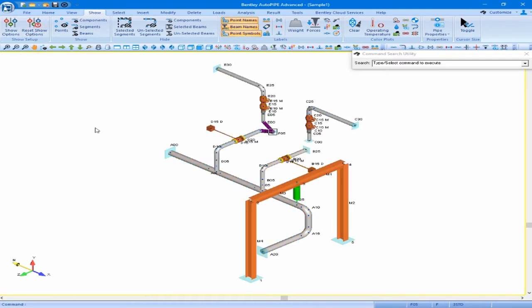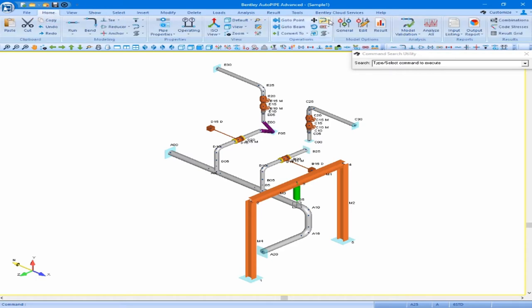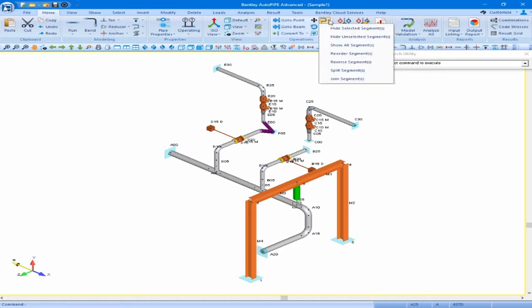Now let's suppose we wish to begin a new segment at point A25 in our model. This might represent the location where the piping system exits the building — creating new segments allows selective application of loads such as wind loads which may only act on a portion of the piping. In order to split the segment, we first want to select point A25 as our active point, then come up to our home ribbon, the segment pull-down menu, and click on the split segment command.